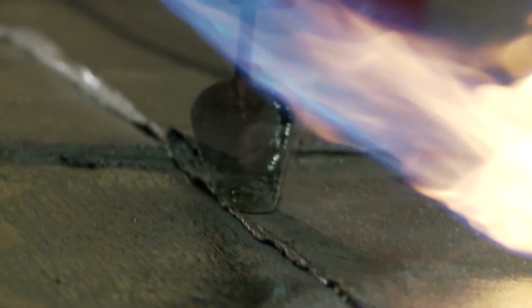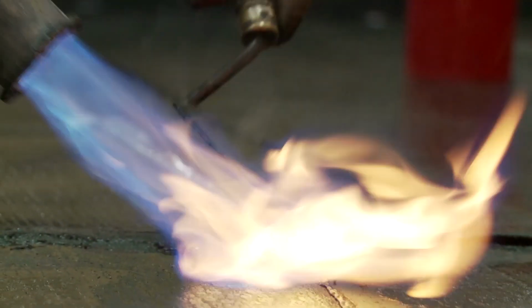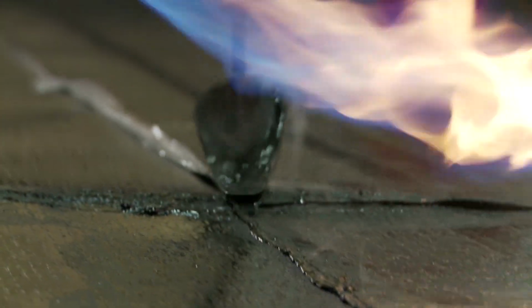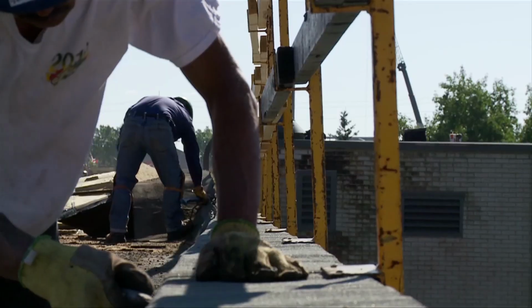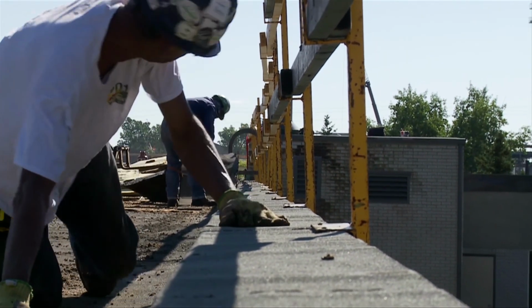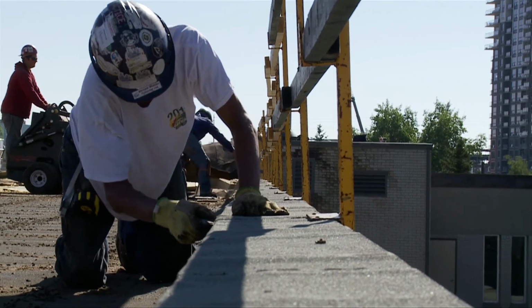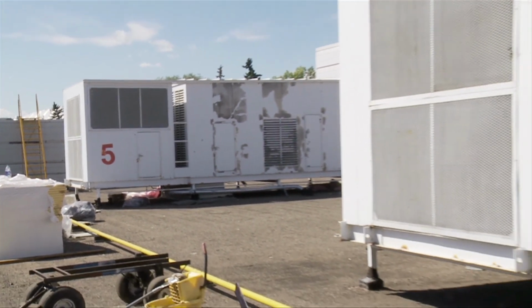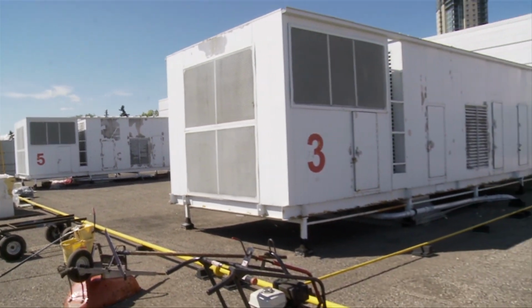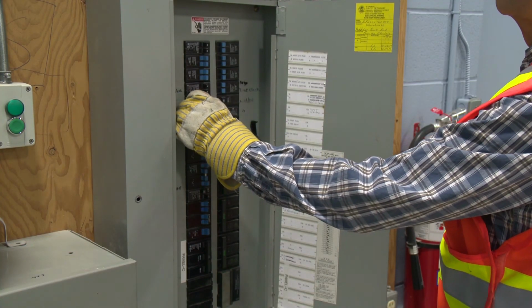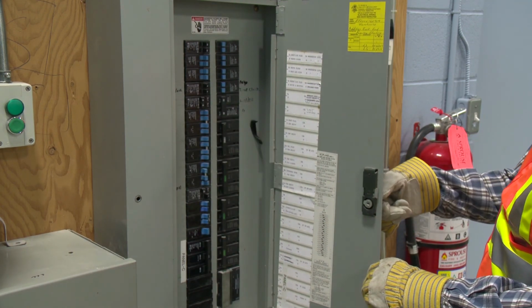As a recap, we will review fire prevention techniques contained within Module 4. Inform building occupants of torching activity. Determine construction, composition of roof and wall assemblies before torching by completing cut tests. Shut down heating, ventilation, and air conditioning units and intake fans in the work area at their control panels and lock off.